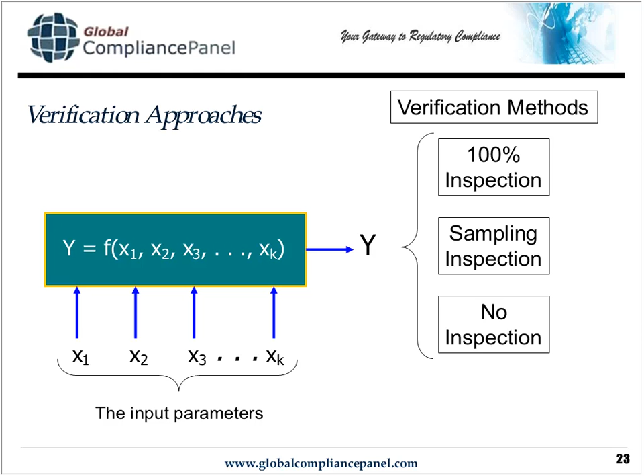I could inspect all the products for all of their characteristics. And oftentimes I find this is what FDA investigators take it to mean, that if I'm not looking at every dimension on the drawing for everything that comes out of the process, I'm not fully verifying. If I've got a complex part with a couple hundred dimensions, that's going to be a bit of a problem. So what oftentimes happens is we have critical to quality characteristics. There's a lot of features on a drawing that if they're slightly out of spec, they're not going to impact the way the part gets used and its ability to function in the medical device. A common characteristic, for example, might be color. If I don't have the paint color exactly right, the medical device is still going to perform its function. So maybe what I have are critical to quality characteristics, and so I'm going to inspect all of the products for the CTQs, not for all of the characteristics.